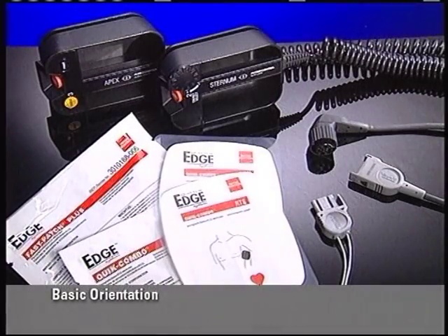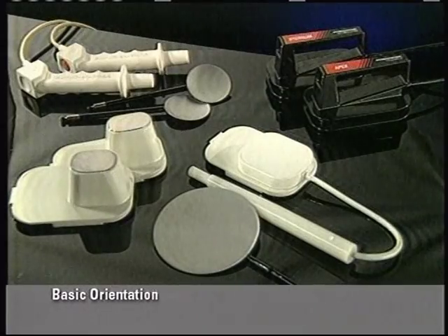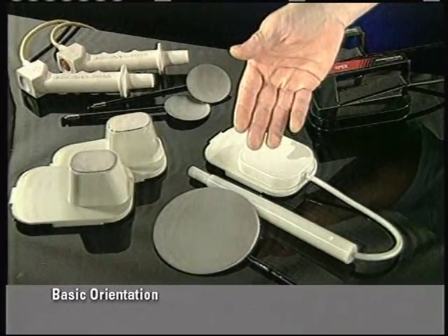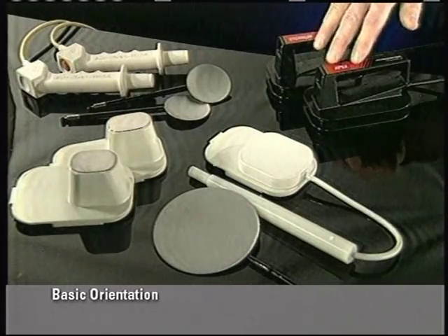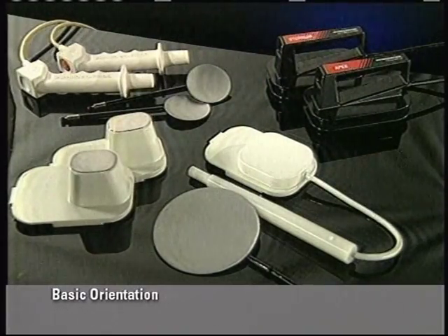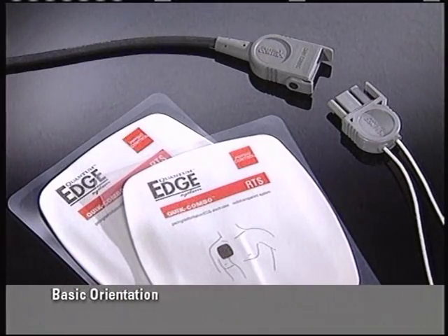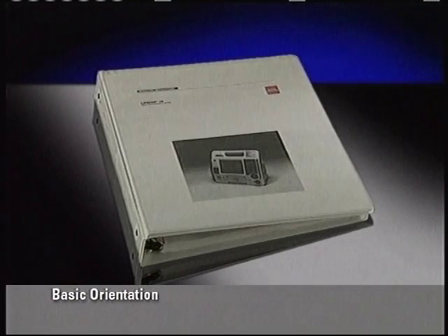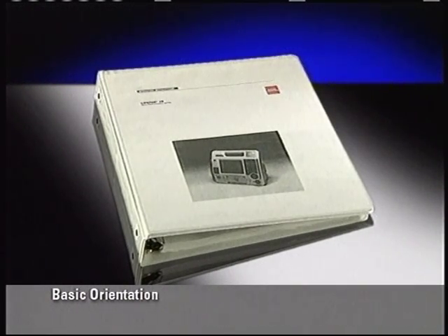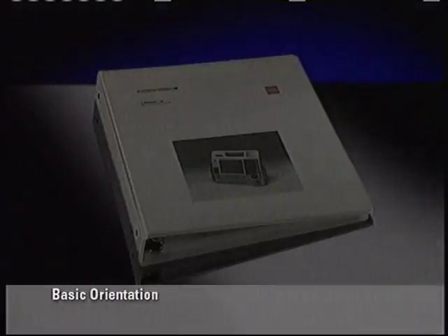The LifePak 12 defibrillator monitor uses QUIK-COMBO pacing defibrillation ECG electrodes, standard adult defibrillation paddles, FAST-PATCH disposable defibrillation ECG electrodes, and pediatric and posterior paddles. Internal and external sterilizable paddles are also available options. Only the QUIK-COMBO therapy cable and electrodes will be demonstrated in this video. Refer to the LifePak 12 defibrillator monitor operating instruction manual for more information about these and the other therapy accessories.